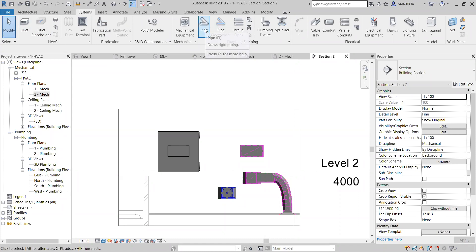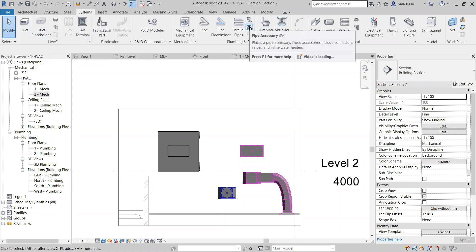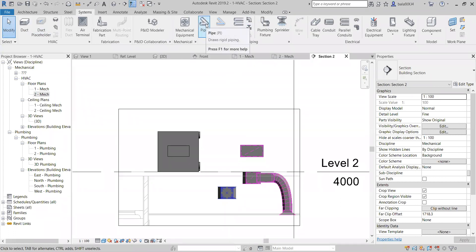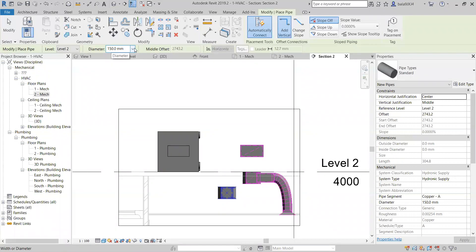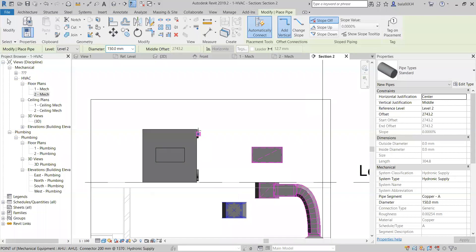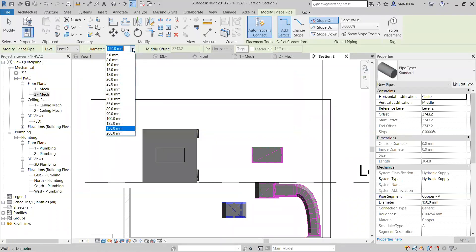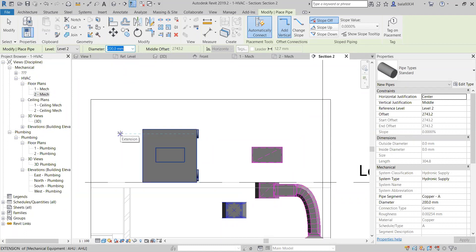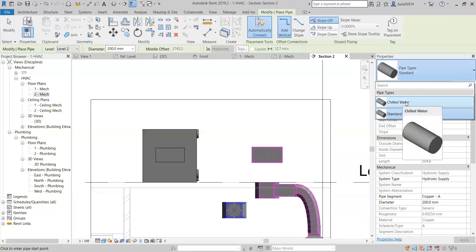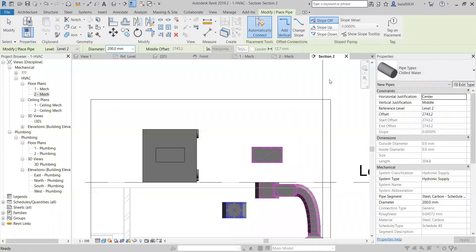I chose the pipe. When I choose the pipe, I get the diameter and elevation of the pipe. I am in the section, so elevation I can choose myself. Here I have a 200mm pipe — I want to draw 200mm diameter. What classification? I need to give it supply — hydronic supply. Here we need to choose the type of pipe. I am going to use chilled water pipe. If you want to create your own, duplicate and make your own — go to Edit Type and select Duplicate. I am going to chilled water pipe, and here you can see the pipe segment: steel carbon, schedule 40, diameter 200. The routing preferences are in Edit Type — here you can see the steel carbon pipe segment, and you can change it there.